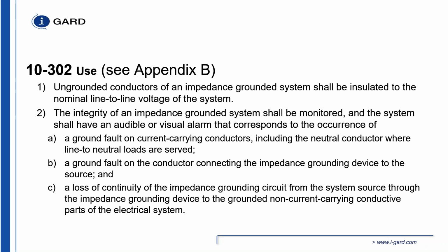What's new in 2018, however, is the integrity of an impedance grounding system shall be monitored, and the system shall have an audible or visual alarm that corresponds to the occurrence of A, a ground fault on the current carrying conductors, including the neutral conductor where line to neutral loads are served. This is relatively new because up until recently, in most jurisdictions, you're not allowed to have a high resistance grounded system when you have a distributed neutral. This is unique to Canada. And I don't necessarily believe it's a good idea to have a high resistance grounded system on a distributed neutral. And I can explain that a little bit later.